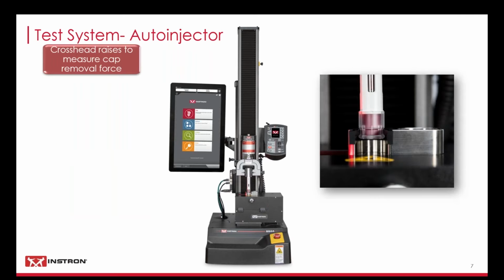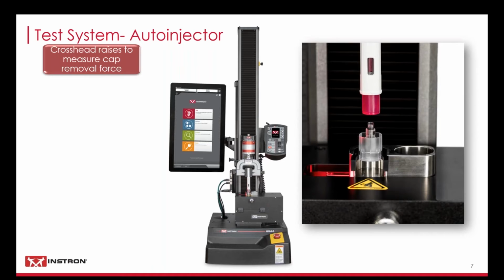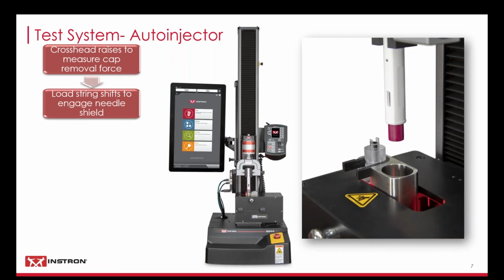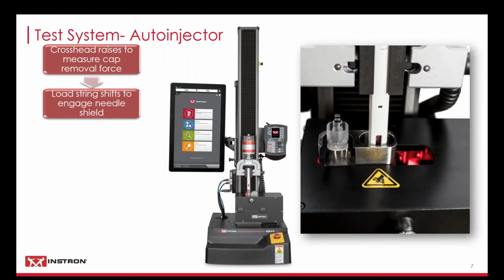This system shows a basic autoinjector test stand. The operator would place the device into the specially designed cap insert and secure it in the grips. Once they press start, the machine will begin the test sequence. First, the crosshead will raise, removing the cap and recording the maximum force. Once the device is clear, the shuttle moves by pneumatic pressure and the crosshead will move down to engage the needle shield. The software will capture the activation force based on user set criteria.